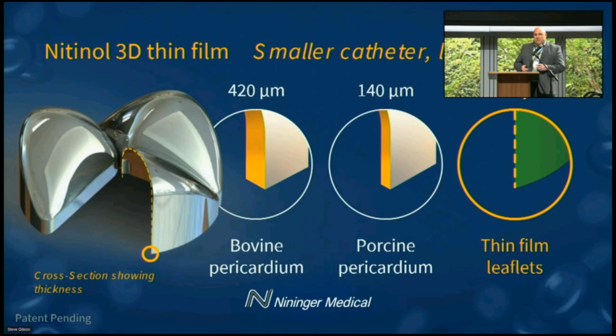We're addressing this by using nitinol 3D thin film technology. And as you can see, our thin film is significantly smaller in thickness. And by having that, it enables the valve to be pushed down into a smaller catheter size. And because it's made of nitinol with its non-porous, very smooth surface, it's naturally resistant to calcification. And because it's an engineered material, it can be mass produced to exact specifications for whatever valve design is required.